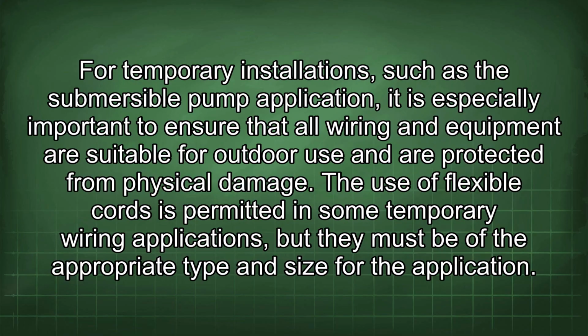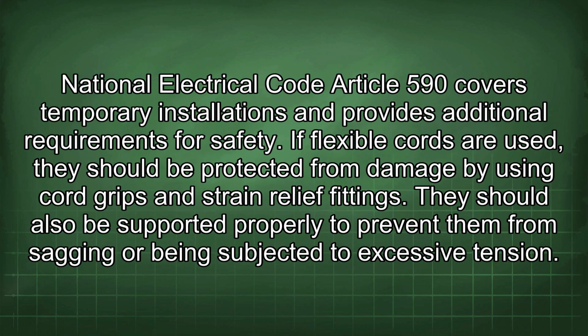For temporary installations, such as the submersible pump application, it is especially important to ensure that all wiring and equipment are suitable for outdoor use and are protected from physical damage. The use of flexible cords is permitted in some temporary wiring applications, but they must be of the appropriate type and size for the application. National Electrical Code Article 590 covers temporary installations and provides additional requirements for safety. If flexible cords are used, they should be protected from damage by using cord grips and strain relief fittings. They should also be supported properly to prevent them from sagging or being subjected to excessive tension.